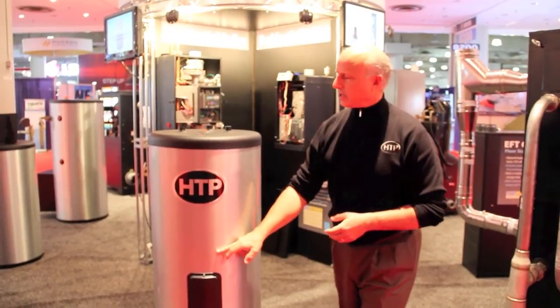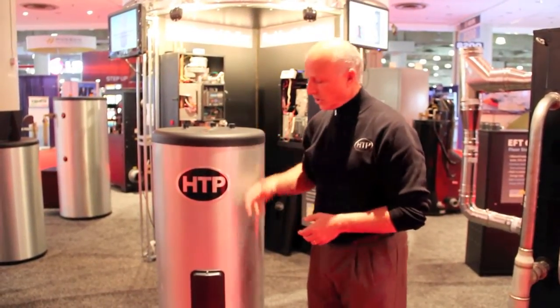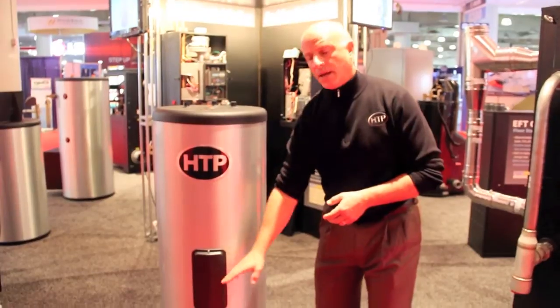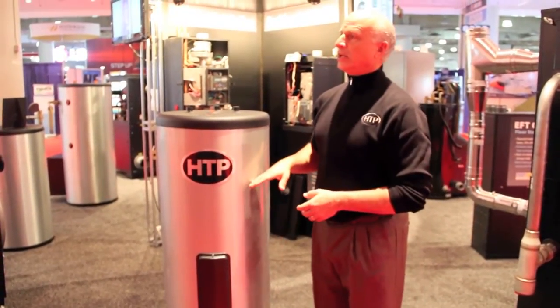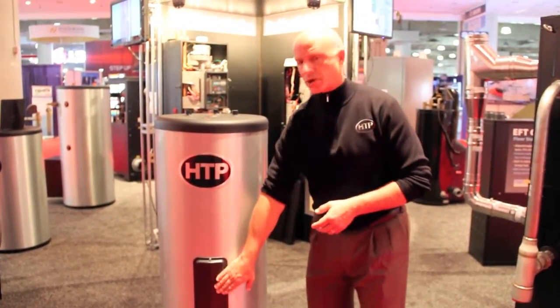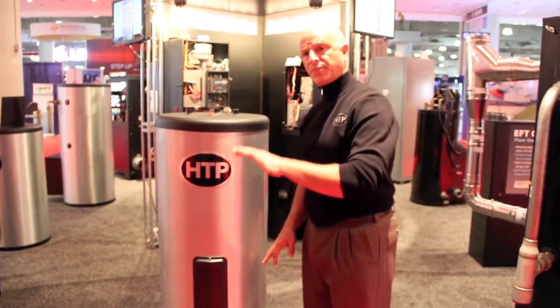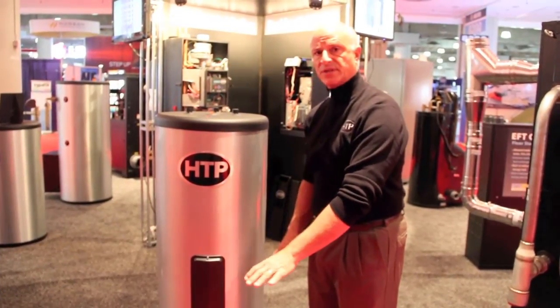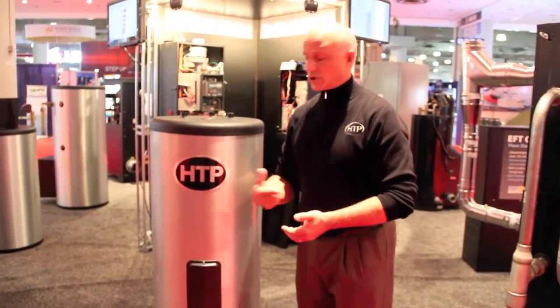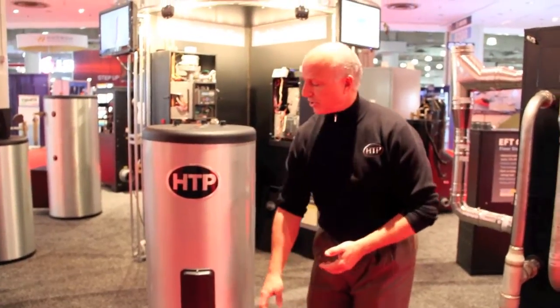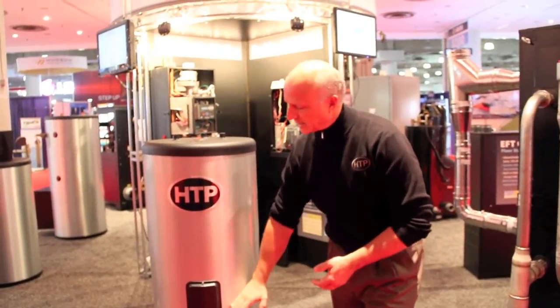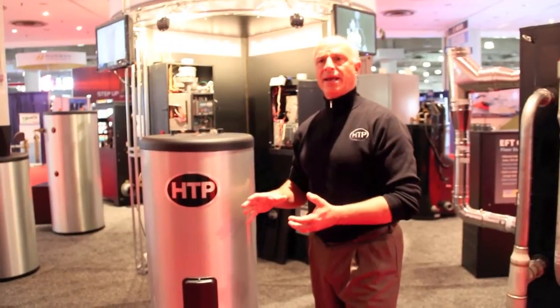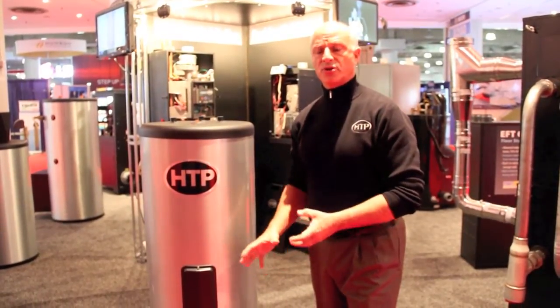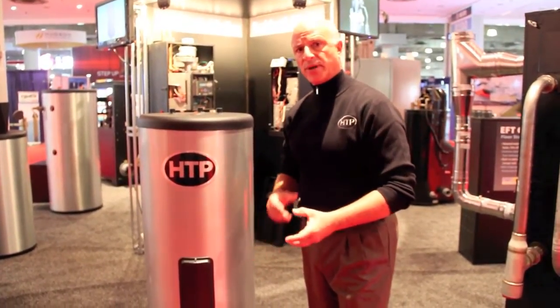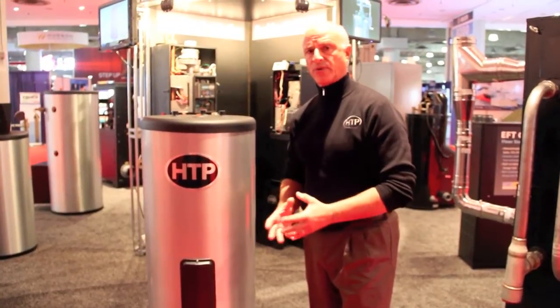When you have a recirc line in the house, most of them get piped into the bottom, and what happens is it causes the unit to fire because there's a control. The control is watching a temperature. If the temperature drops below 5 degrees of its set point, it's going to fire the boiler, and the circulator is going to circulate water to the heat exchanger. The problem with that is that the tank is still warm, so we're not getting the efficiency out of the heat exchanger. It causes these low mass, high performance boilers to short cycle frequently.